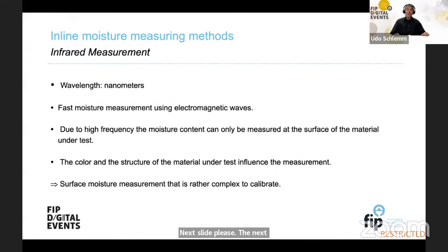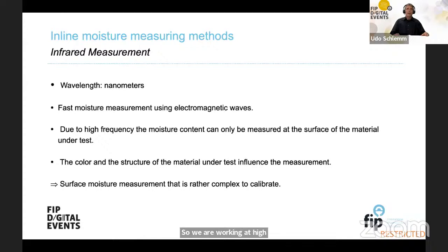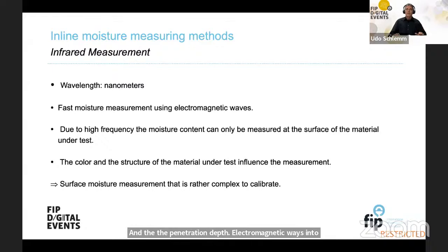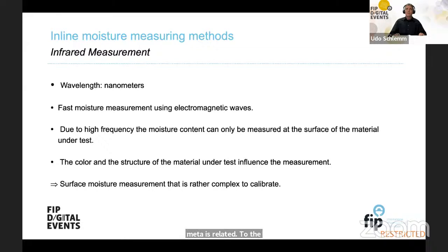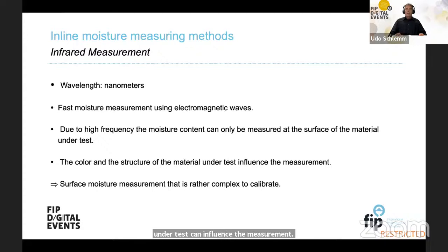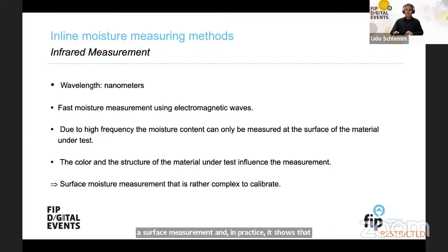The next well-known method is infrared measurement. We work at high frequencies where the wavelength is only nanometers, and the penetration depth into matter is very shallow — it is a surface measurement and cannot penetrate deeply into the matter. The color and structure of the material under test can influence the measurement, and in practice it is rather complex to calibrate.